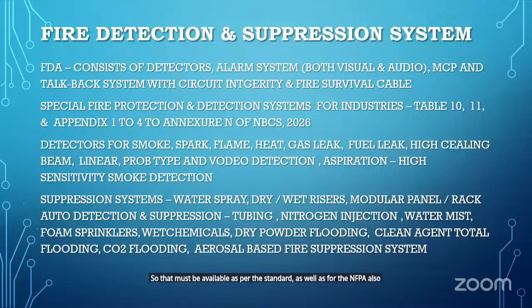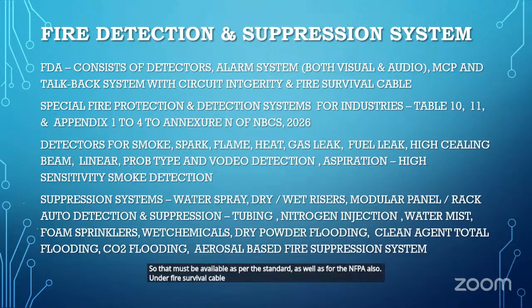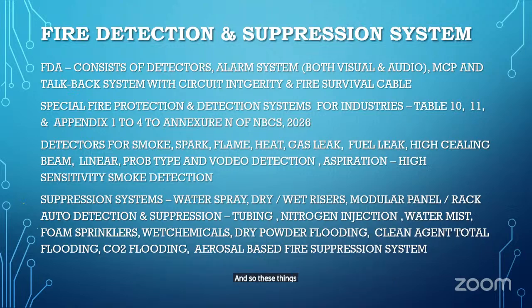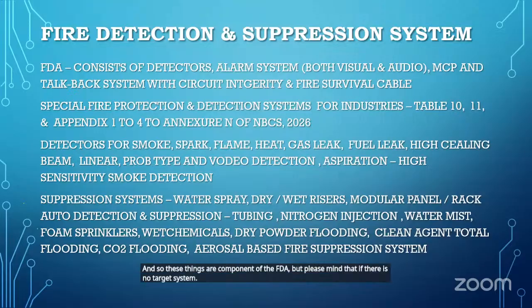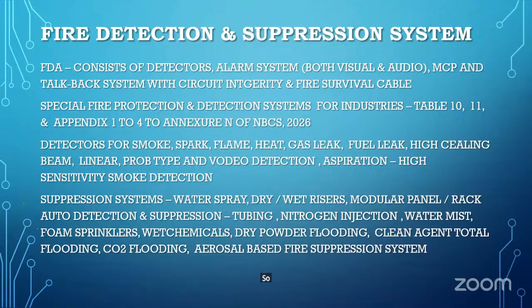And the fire survival cable, especially for detectors and the alarm system, you should provide survival cable, which will not be affected immediately by the fire. That is a fire survival cable, a fire rated cable. These things are components of the FDA. But please mind that if there is no talkback system, you are not compliant. If there is no circuit integrity, you are not compliant. If your cables are not fire survival cables, you are keeping a fire detection system only for formality. That will not work in reality. That's the thing I want to convey to you.